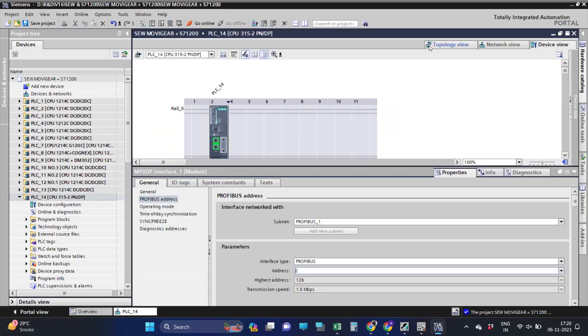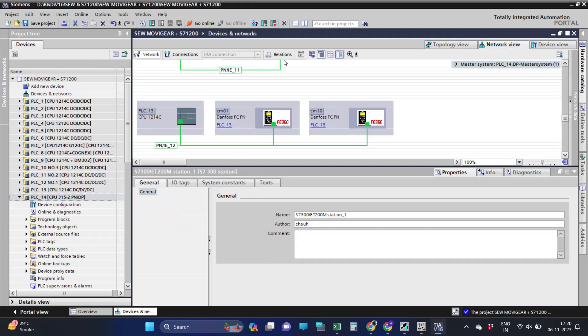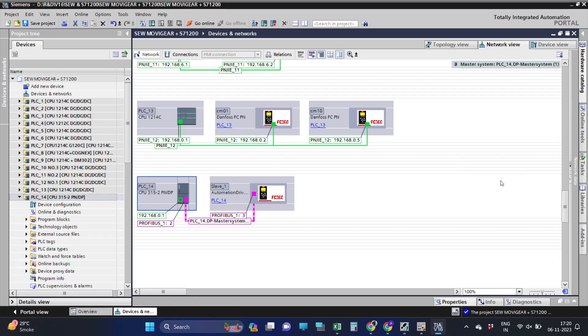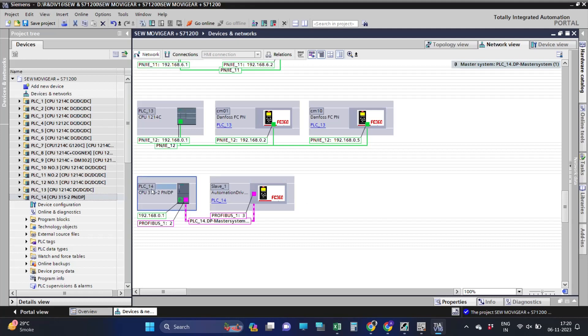As we can see, we have successfully added the CPU and the drive in the Profibus network. Profibus node address 2 is assigned for the CPU and for the drive, node address is 3.